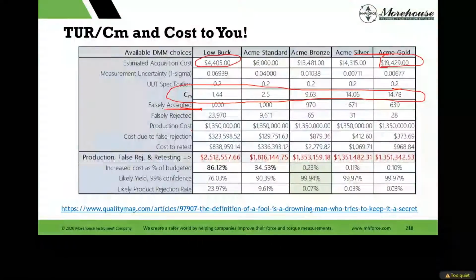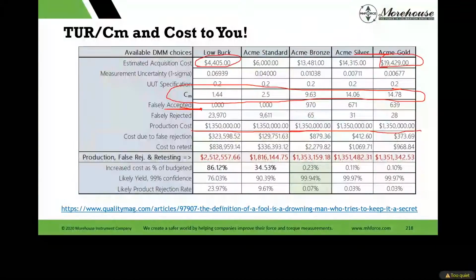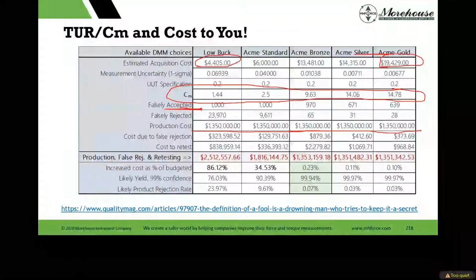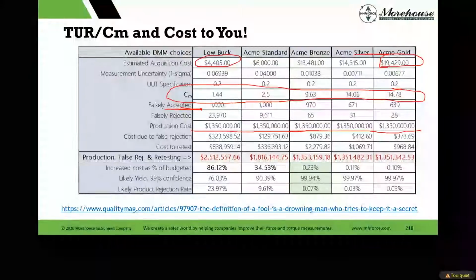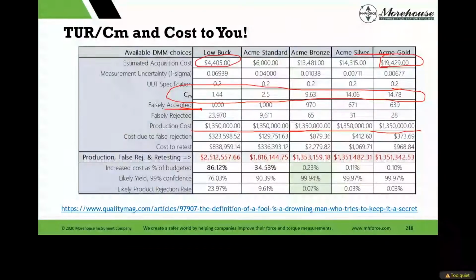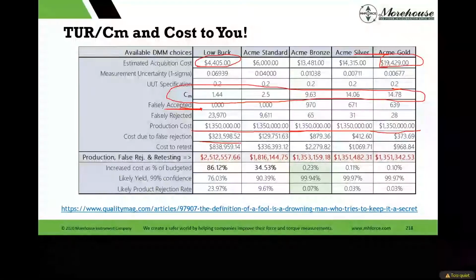Our production cost, or your calibration cost, if you think about it per the lab view, stays the same, right? As far as if somebody pays me for a calibration, you might have adjustment criteria, but just say somebody pays you a flat fee for the calibration, or you're making this resistor widget. It's going to cost us the same on that side of things. If I false reject it, which means I say it's bad when it's actually good, what are you going to do? You're going to adjust it and send it to the customer. That adjustment costs money. If it's a false accept, then you're going to send them bad. This is a production example, so we're rejecting resistors here. I've rejected enough resistors that it's costing me $323,000 per month.